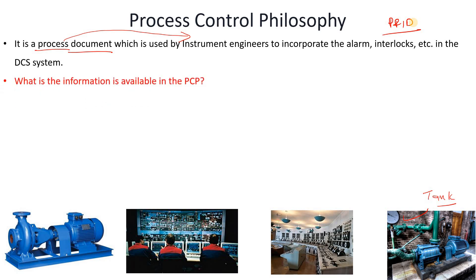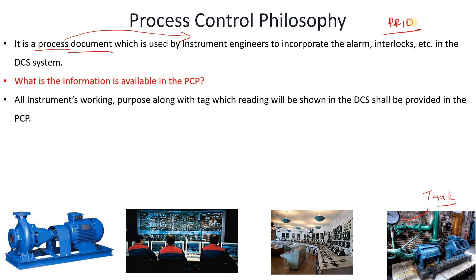The information available in the process control philosophy includes all instruments seen in the P&ID that will be read in the DCS — for example, PT, LT, TT, control valves (level control valve, flow control valve, pressure control valve), and analyzers.